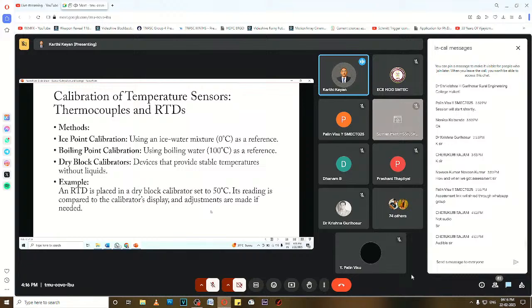And another one is boiling point calibration. If it shows 100 degrees Celsius, it will be a perfect one. Next to that is dry block calibrators, devices that provide stable temperatures without liquids. That is what it means. So the reading has to always show 100 degrees Celsius. Each time you put it in boiling water, it has to show 100 degrees Celsius.